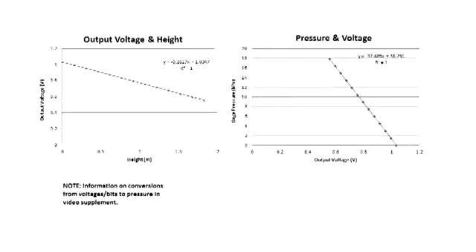These calibrations will also help you make sure that your instruments are working because you'll be able to see and make sure that the fits are linear on your calibrations, and make sure values are within range.